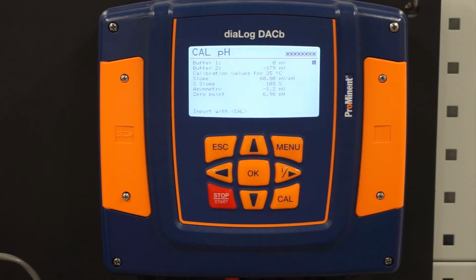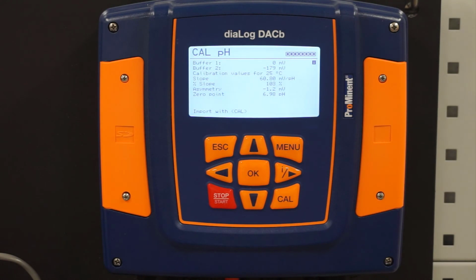So if we pay attention to this, we should be able to get an idea of when we need to order a new pH sensor, because we don't want to stock pH sensors. They are like batteries. Even if we're not using them, they will start to lose their charge. So maybe if we start getting down to 30 or 25% slope, we would order one, and when it came in, we would install it and replace the one that's currently in there. We have to make sure we import the calibration. If I were to escape from here, we would abort the calibration. So if I continue with cal, it is now successfully calibrated for our pH.